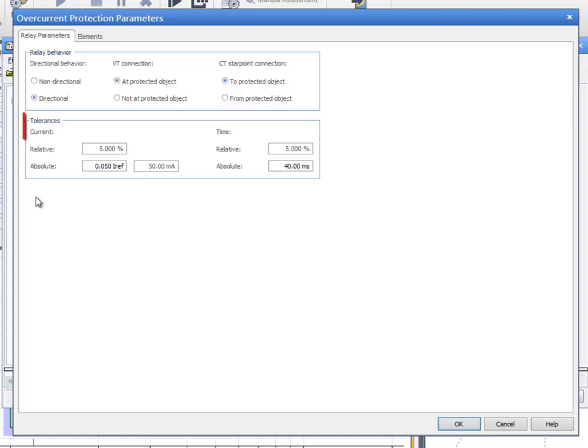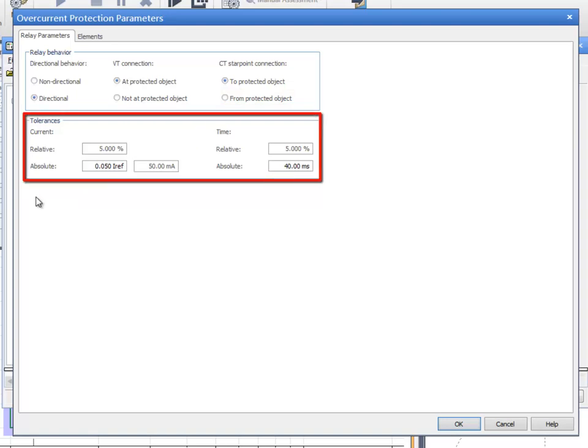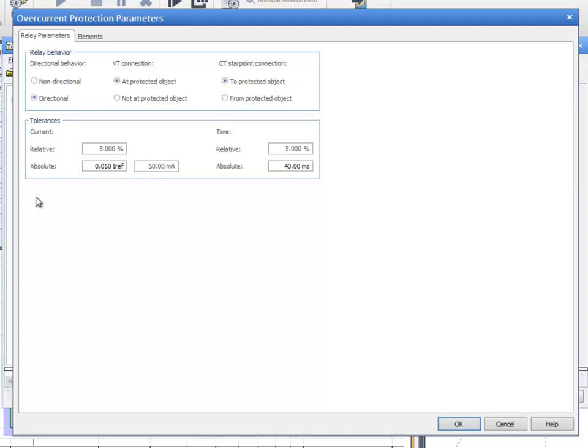Enter the current and time tolerances according to the Relay's manual. These tolerances can be defined as either absolute or relative values. Relative is a percentage of the setting value. Absolute is a constant value that is defined as a multiple of the reference current. The reference current is linked to the nominal current by default.